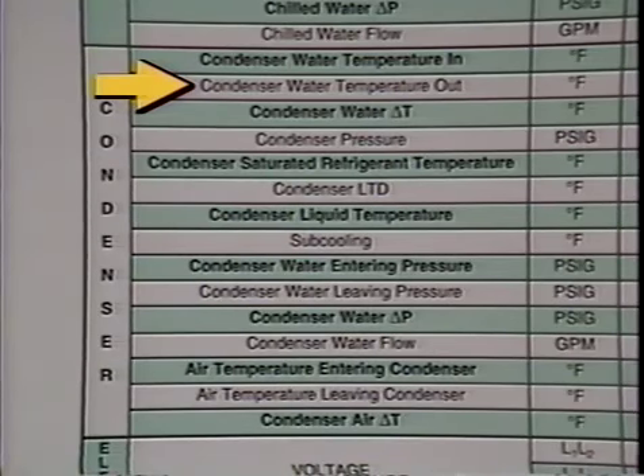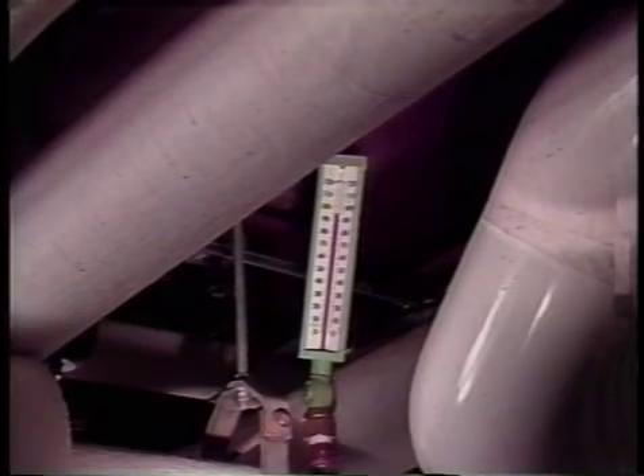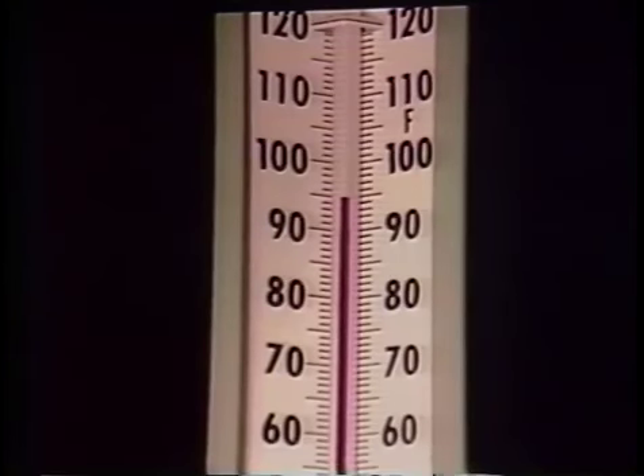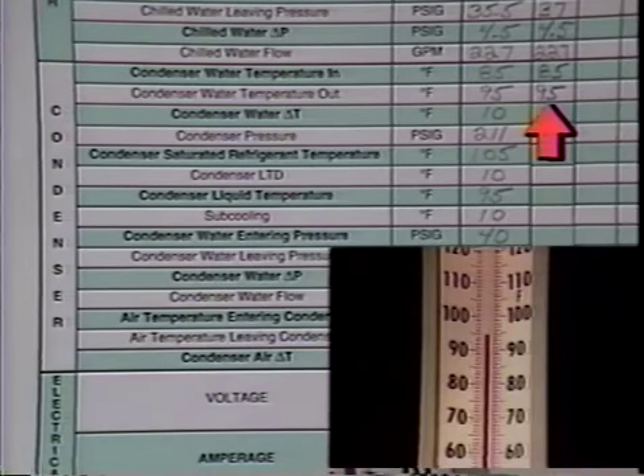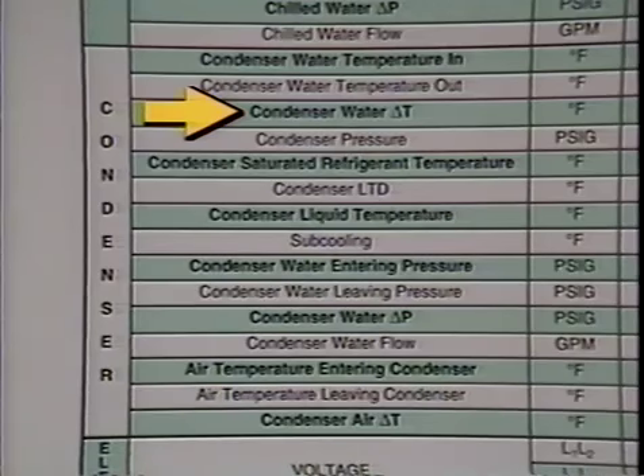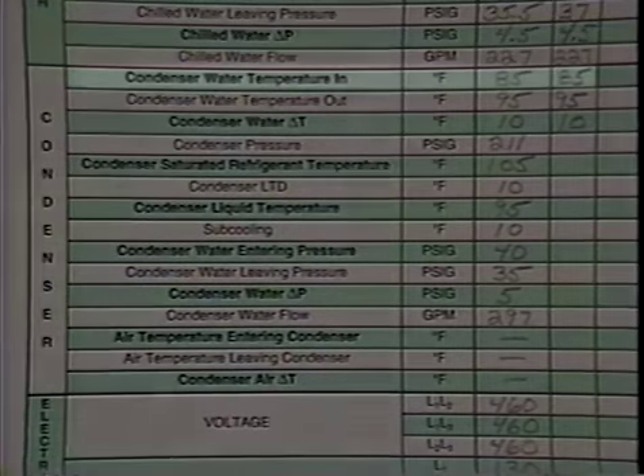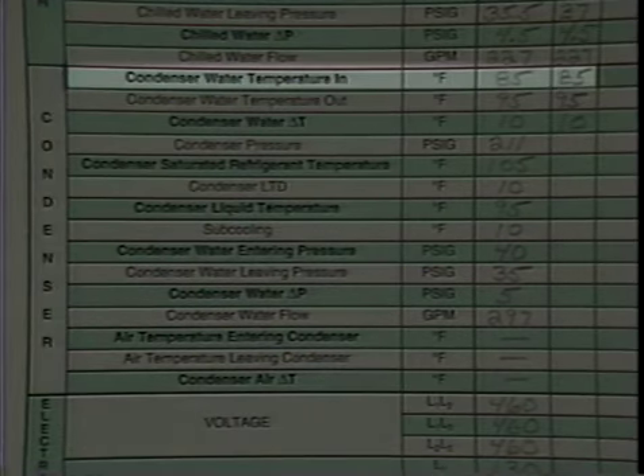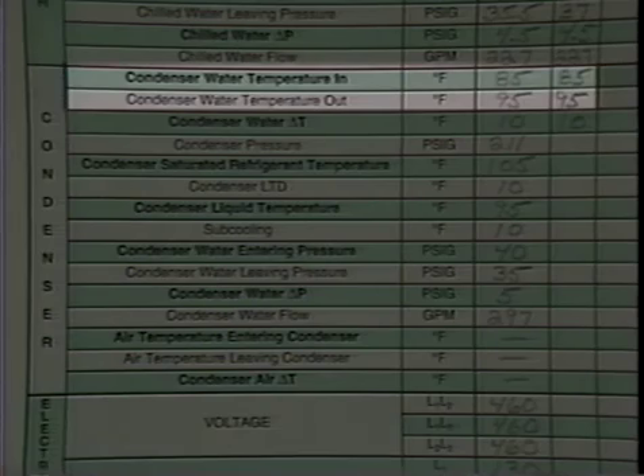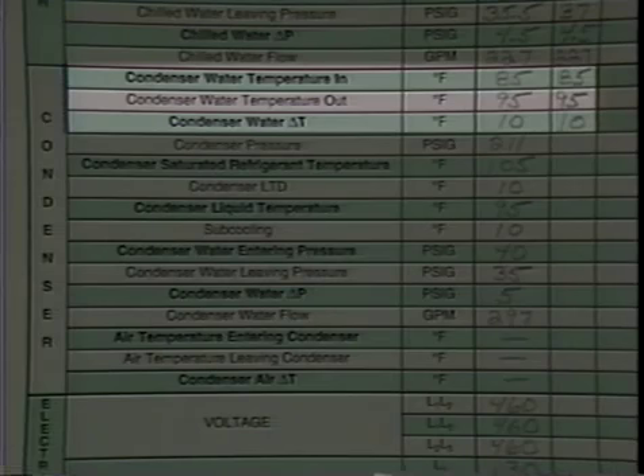Water temperature leaving the condenser. This temperature will vary with the heat load and/or tonnage. Under full heat load conditions, it should not exceed design. Under less than full heat load conditions, the temperature will be less than design. Condenser water delta T. Next, we'll find the condenser water delta T. Do this by subtracting the entering condenser water temperature from the leaving condenser water temperature. Condenser water delta T provides an indication of condenser heat rejection.